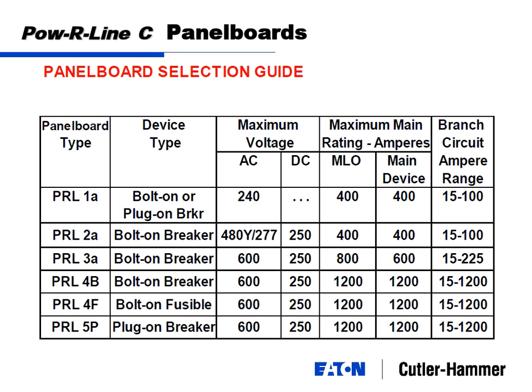1 and 2 are very similar, lighting and receptacle type panels, and then you get up into the 4s, which are the power distribution panels. The difference being you jump up to a 600 volt rating. Your amperage ratings go from 400 amp for the small ones up to 1200 amp for the large ones. And you can see your branch circuit breakers also go from 100 amps maximum on the low ones to 1200 amp maximum on the larger ones.